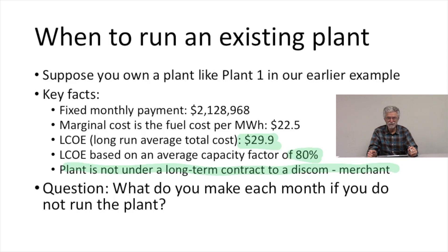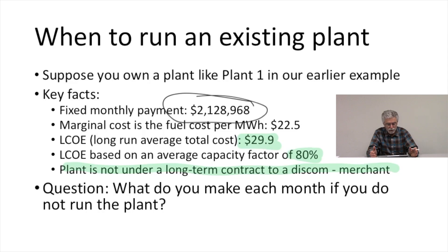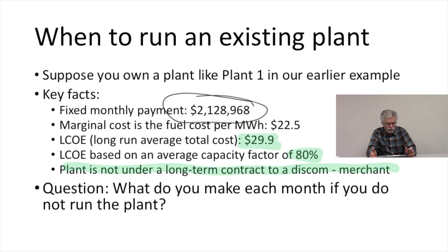Well, this is a trick question of course. The answer is that you earn a negative amount — that is your fixed payment that you have to make each month. If you don't run the plant you don't have any variable costs, but you still have your fixed costs of $2,128,968 every month. You have to write the check whether you run the plant or not. You make the negative amount equal to your fixed costs — the contract costs you had to pay to get this plant built.